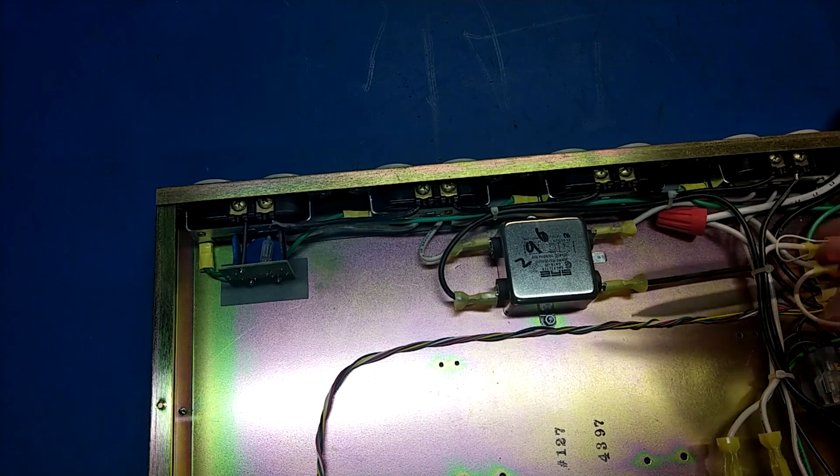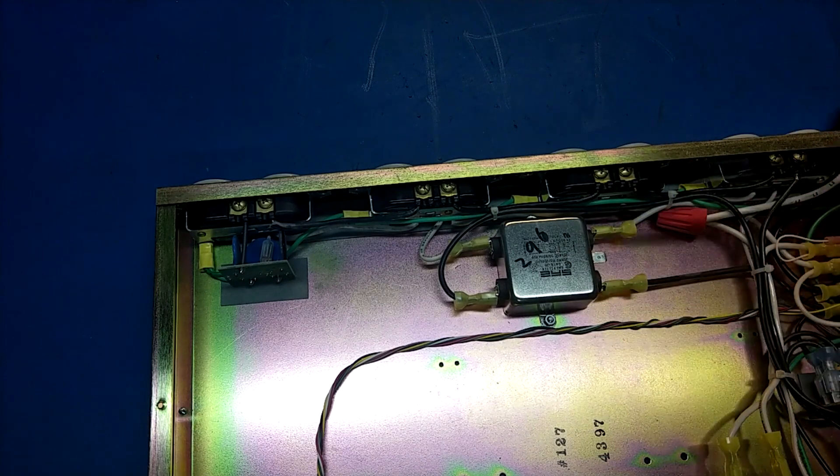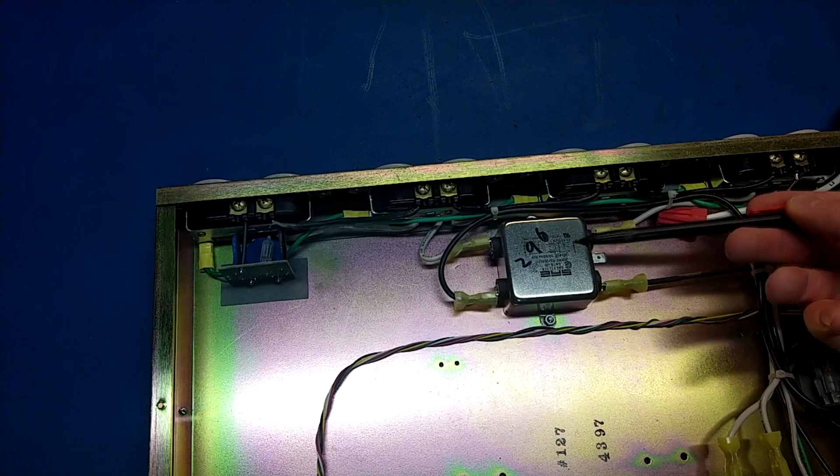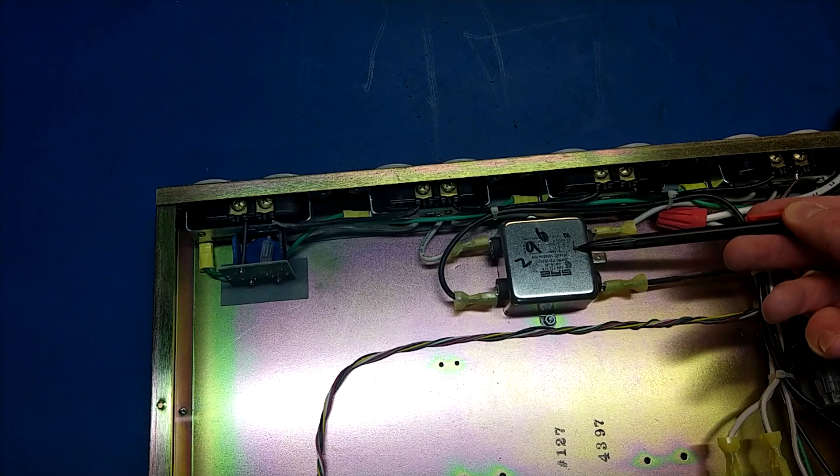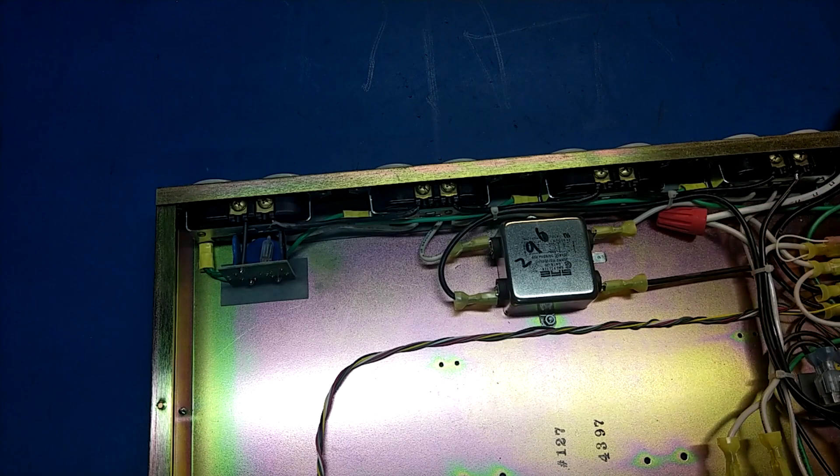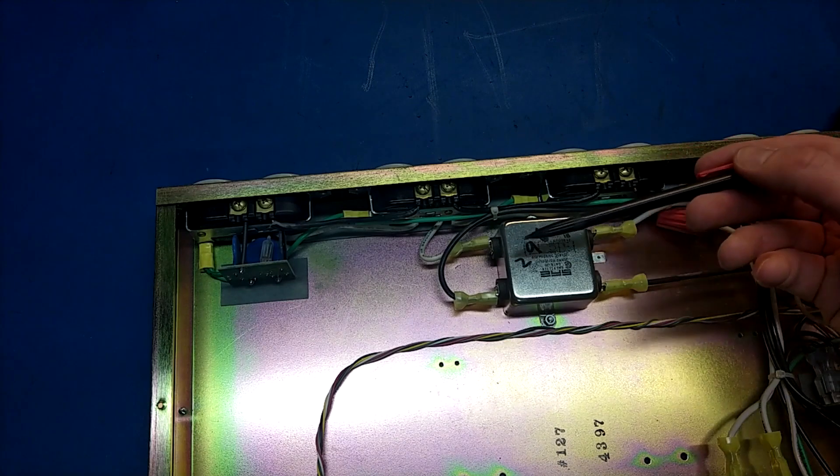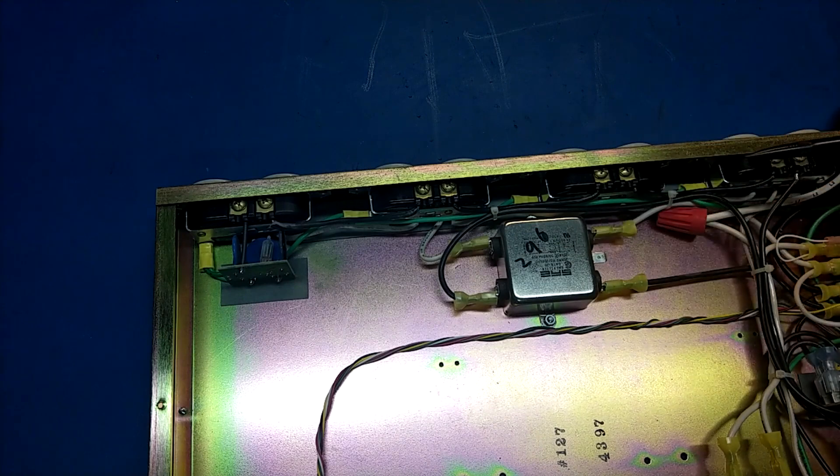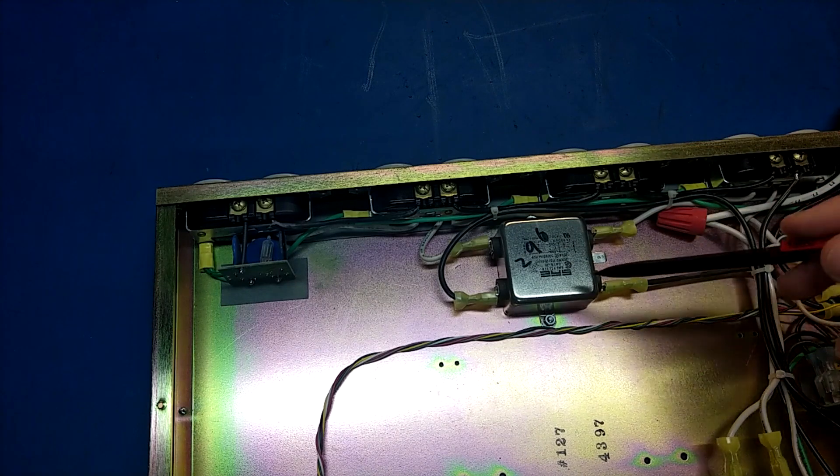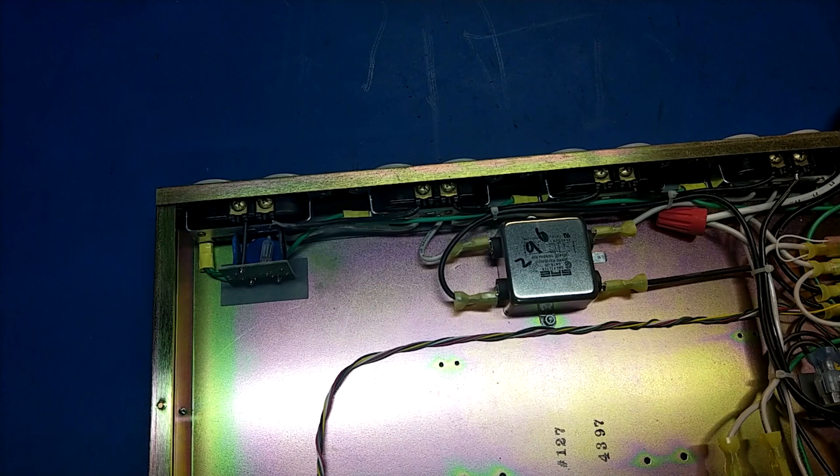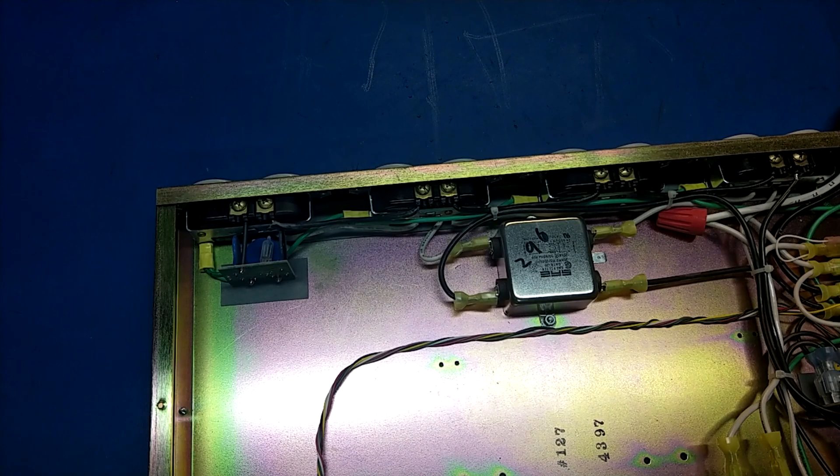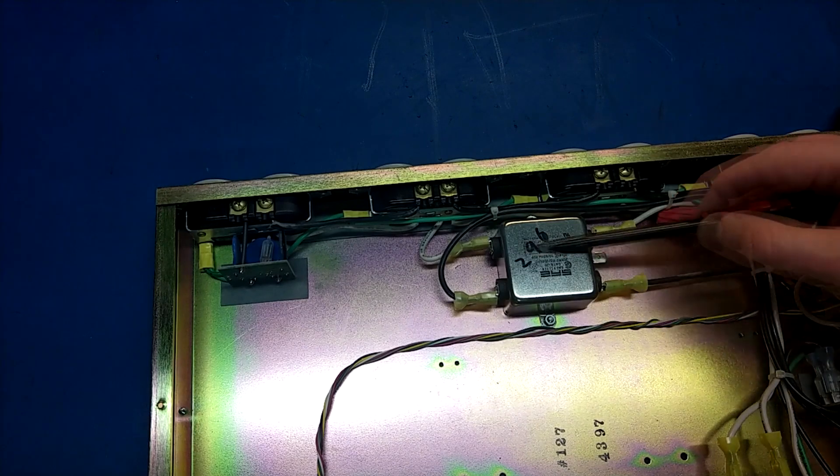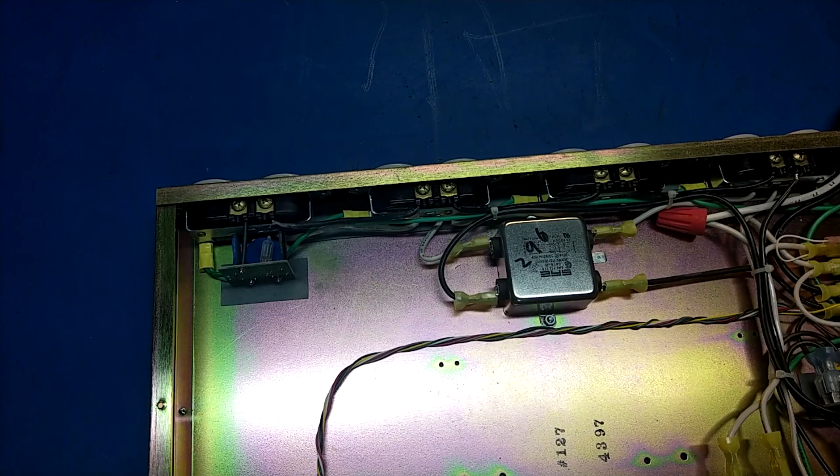So that's the line filter and that's all it's doing. The whole purpose of these is just to be basically a low-pass filter. You want your 60 Hz AC to get through, but anything generally above 60 Hz you want to start filtering out. And these usually are good up to several hundred kilohertz I believe in terms of noise filtration going through the unit.